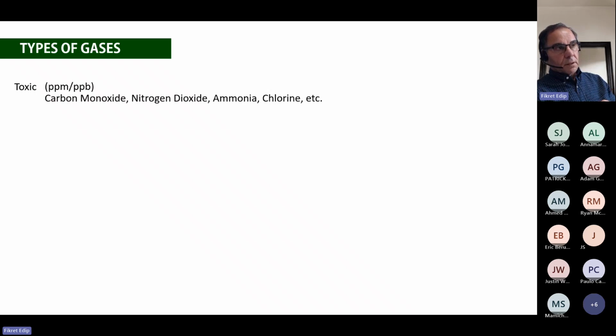And then we have ammonia. We all heard about the ammonia gas leak in Fernie, British Columbia a few years ago. Unfortunately, 4 workers lost their lives because of the massive ammonia leak in a hockey arena, I believe it was. And then you have chlorine and many other types of toxic gases. So toxic gases go into the first category. Second is combustible gases. Combustible gases are typically measured in percent LEL. LEL stands for lower explosive limit, and I'll be talking about it briefly soon. The gases are methane, propane, hydrogen, and many other combustible gases that, if they leak and reach their LEL in terms of the concentration, and you have a spark and oxygen, obviously, then you have an explosion.